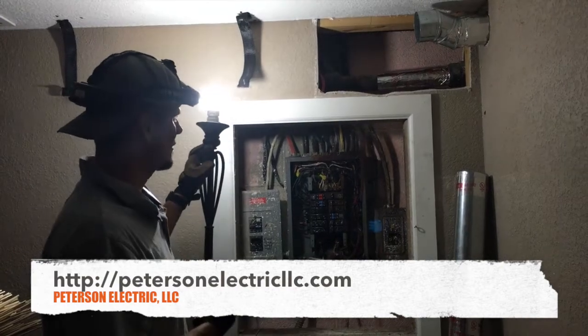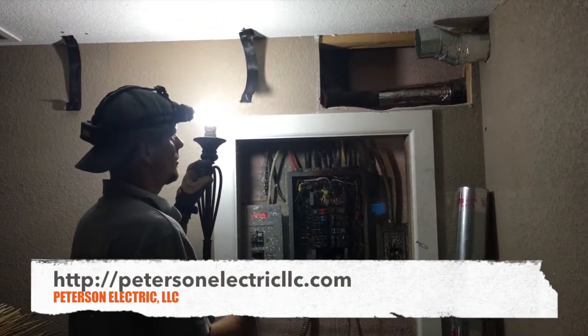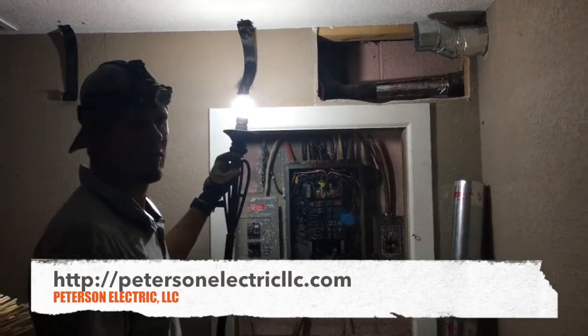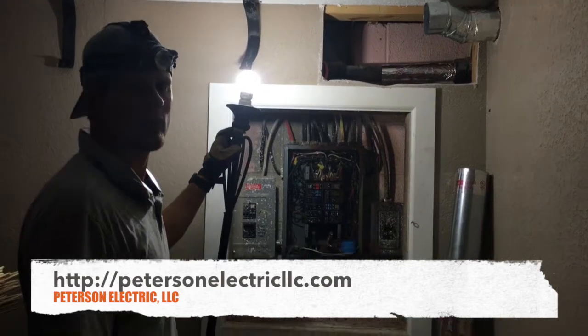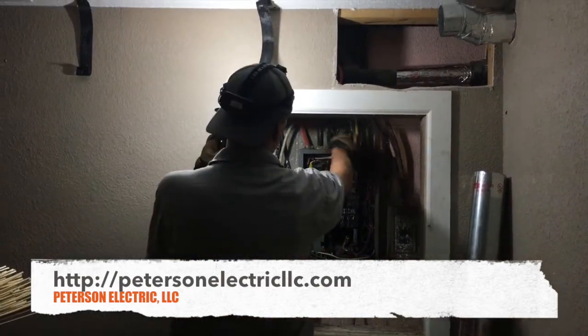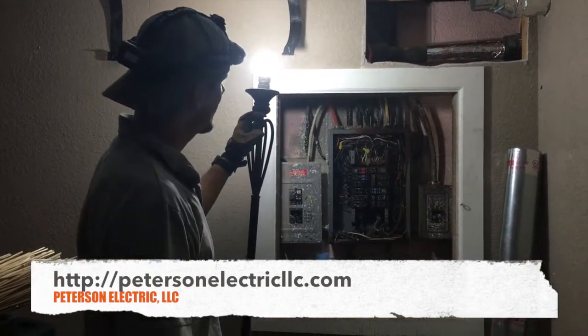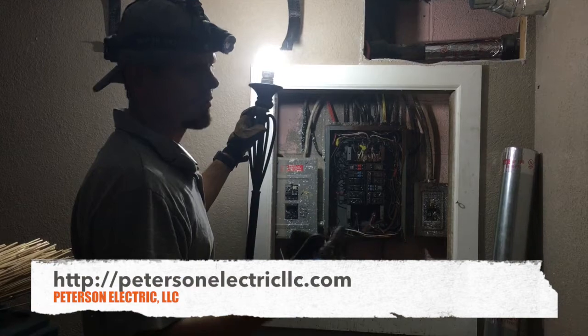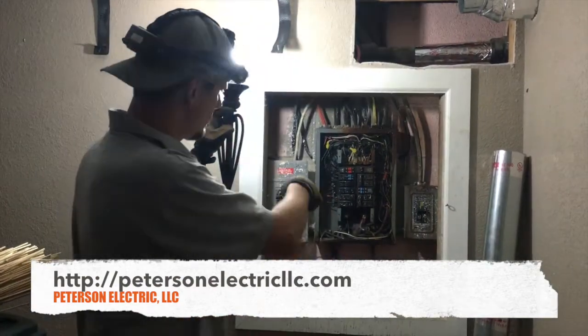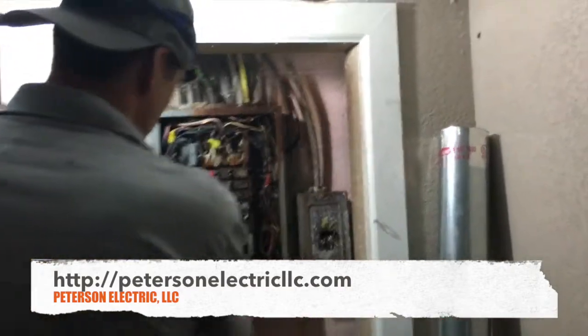But this, boy, even if this panel has to stay here, because if the panel moves more than 6 foot, the whole house has to be arc-faulted. But none of the circuits have grounds anyway. And even though they came and ran a 12-2 yellow and a 10-2, 10-3 orange conductor cable with grounds, there is no grounding for it to go to. But the whole panel is full. If you can see this again, it is full of water.